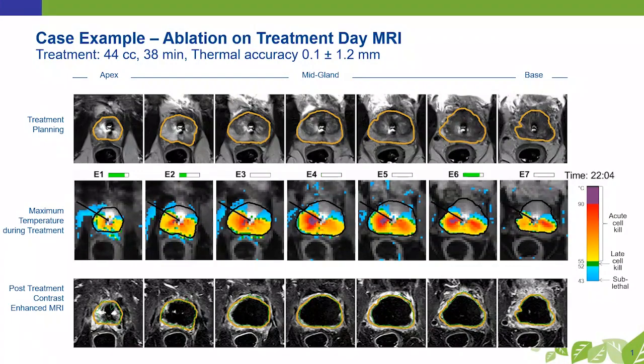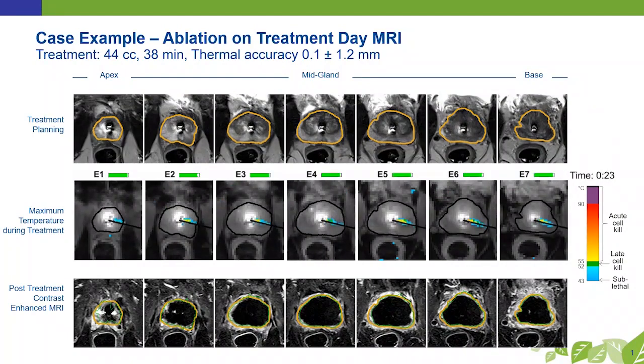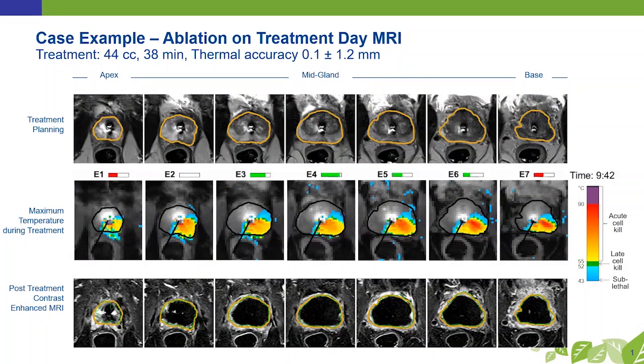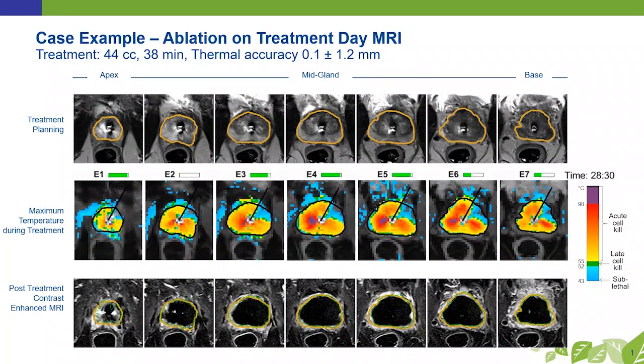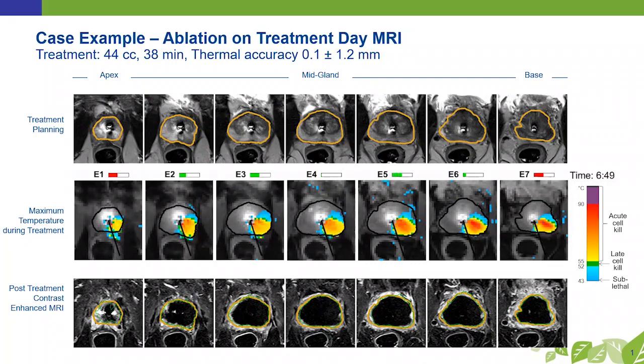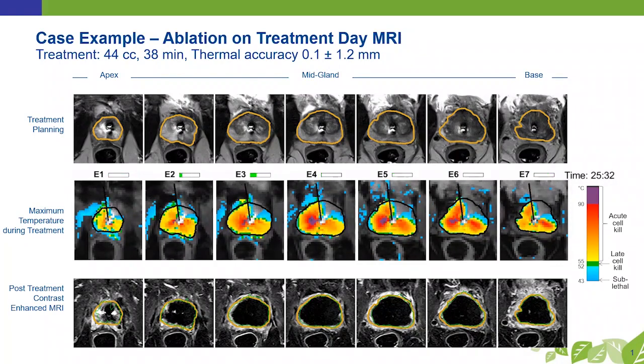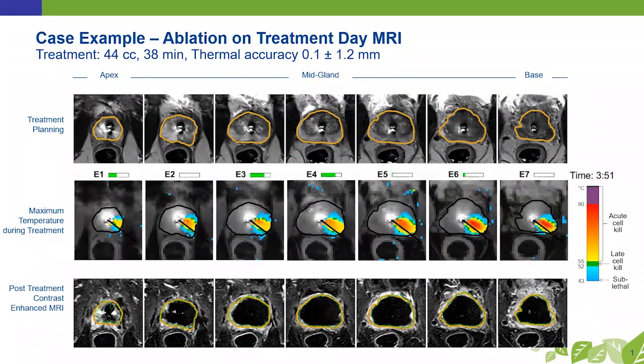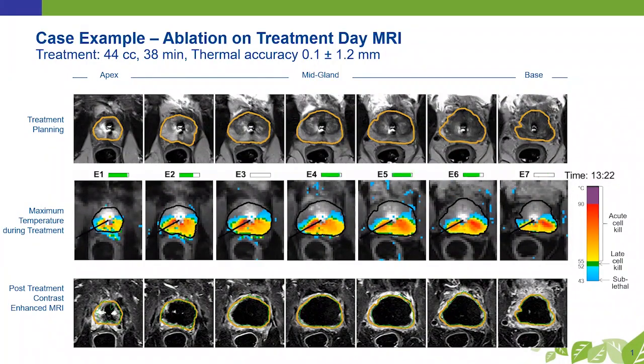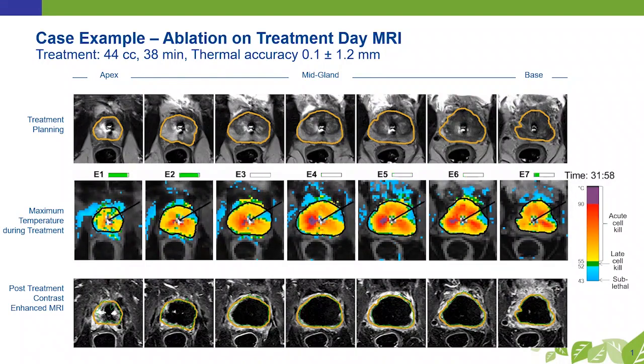tissue target. On the top row, you see for each one of the 7 slices, so this was a 3.5 centimeter long target area. Each slice has the target outlined in the brownish color there. The next little row that says E1, E2 shows the power in that slice while you are watching the procedure being administered. The third row shows the maximum temperature during treatment. If we can now activate this, you'll see this is considerably speeded up. But what happens is the energy is delivered to each one of those 7 transducers. You can see the yellow thermocline moves out to the target, which is in black, and then it stops.